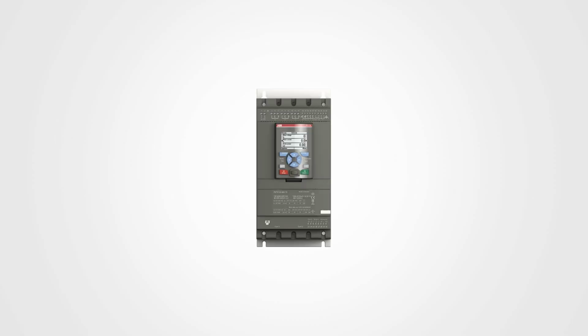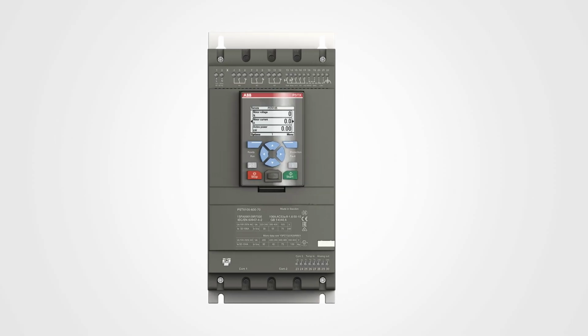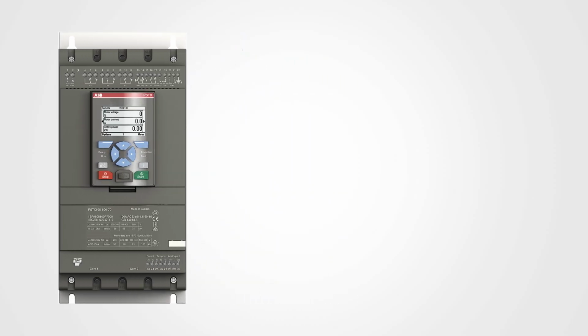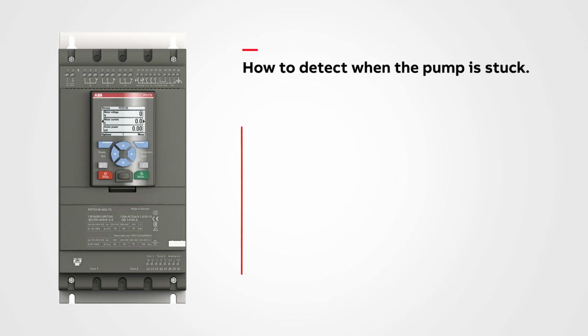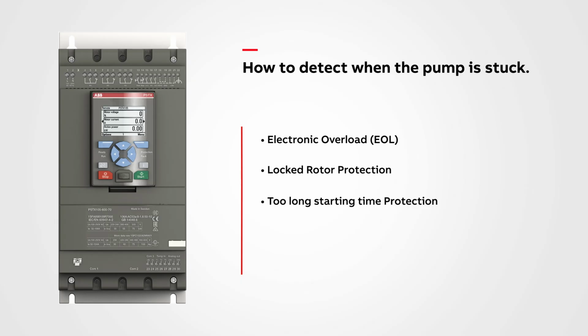To detect any issues with the pump, it is recommended to use one of the following methods. When an object is stuck in the pump, the motor will draw more current, causing the soft starter to trip on electronic overload, EOL, or locked rotor protection. Another indication of a blockage is if the soft start takes too long to ramp, or if the pump stays at the current limit for an extended period. These 2 symptoms can be programmed in as a protection within PSTX.